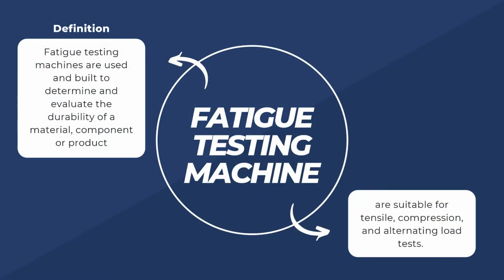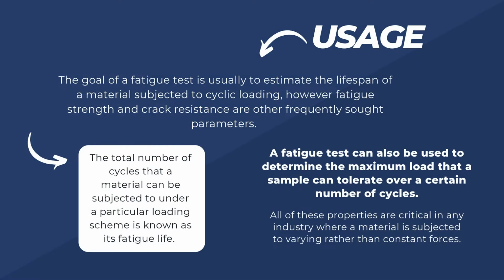First equipment, we have the fatigue testing machine. Fatigue testing machines are used and built to determine and evaluate the durability of a material, component or product, and are suitable for tensile, compression, and alternating load tests. The goal of a fatigue test is usually to estimate the lifespan of a material subjected to cyclic loading. However, fatigue strength and crack resistance are other frequently sought parameters.